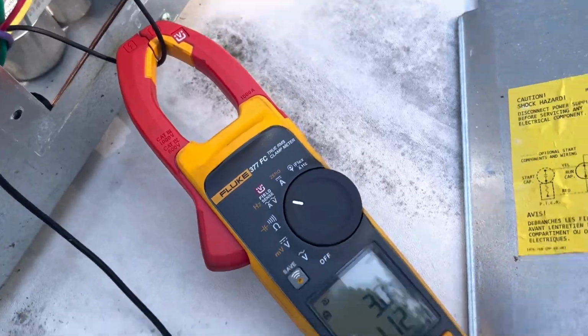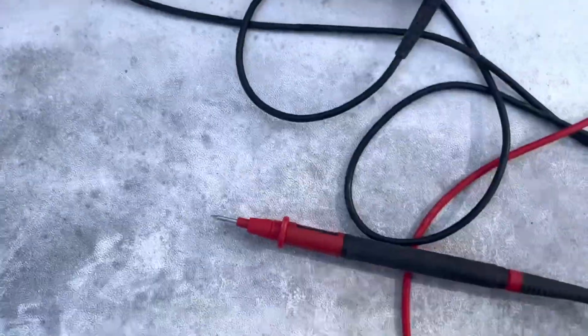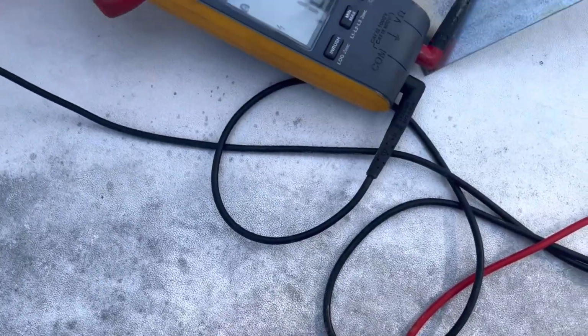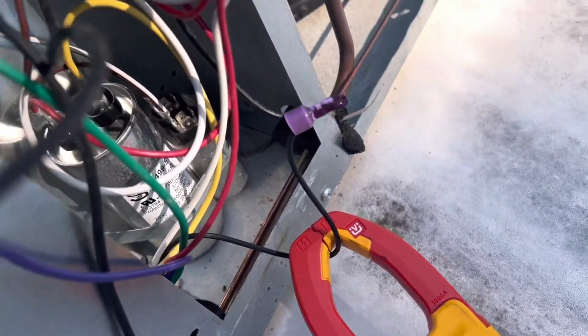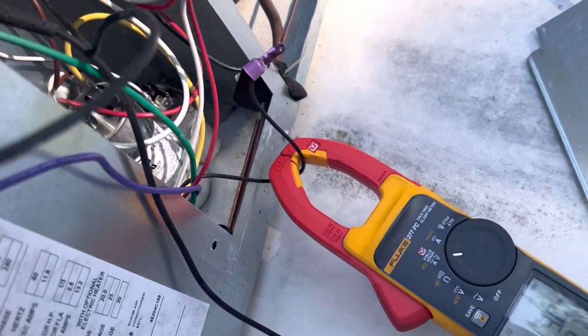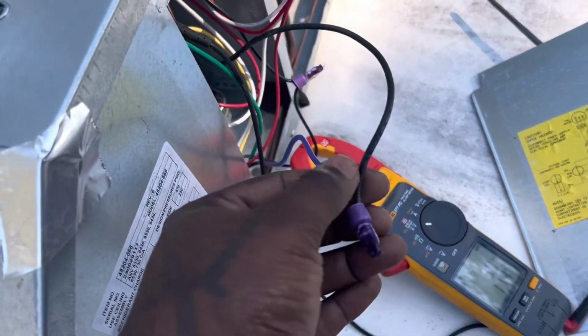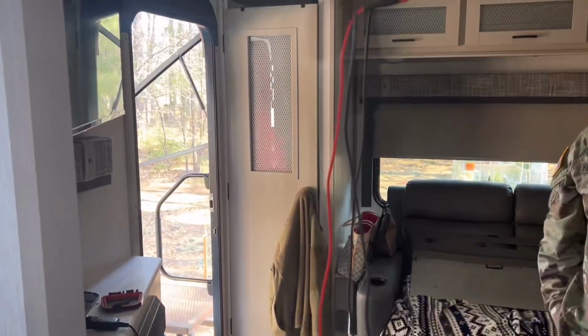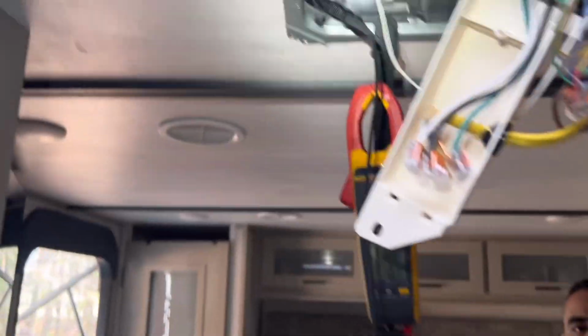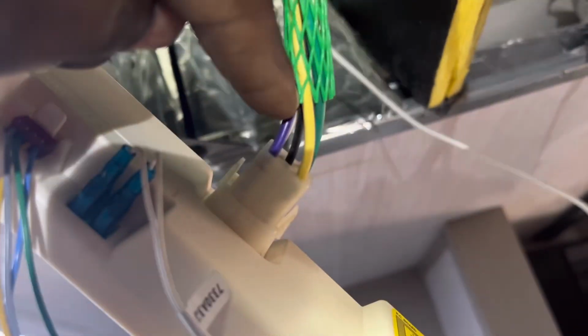Just to be sure, I went ahead and also used the leads to check it. That's going to definitely be a little more accurate, but I am getting 120 volts coming in on the fan side, getting nothing on the compressor side. Okay, troubleshooting the control box. Up top, I do not have any 110 power coming out on the purple wire, and I still don't down here.